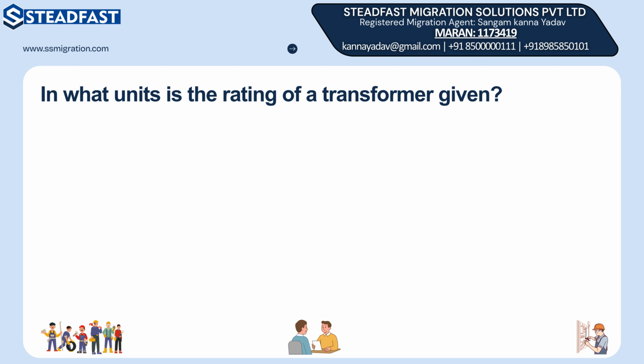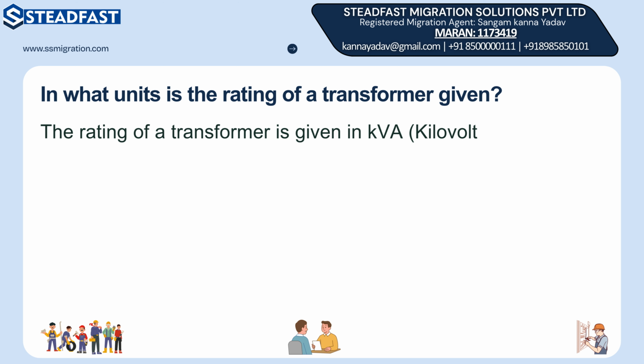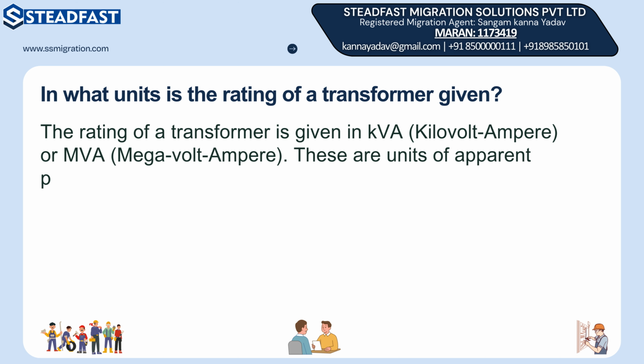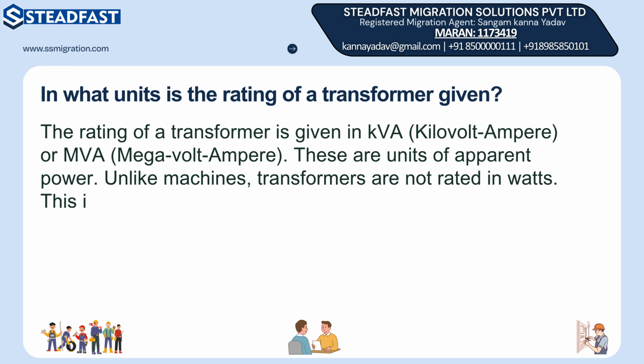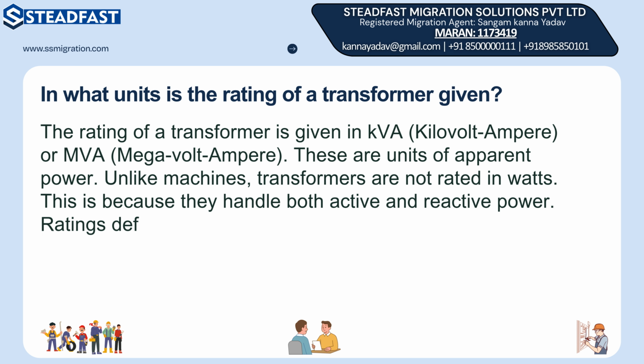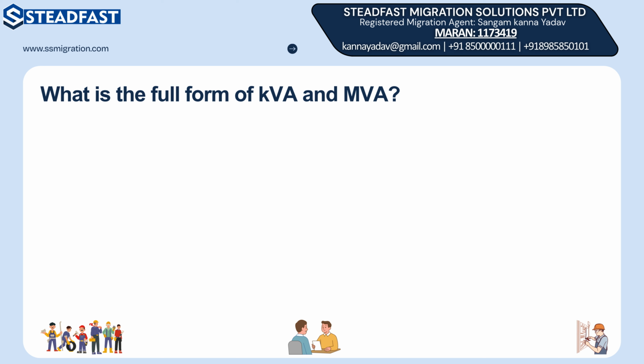In what units is the rating of a transformer given? The rating of a transformer is given in kilovolt ampere or megavolt ampere. These are units of apparent power. Unlike machines, transformers are not rated in watts. This is because they handle both active and reactive power. Ratings define transformer capacity.